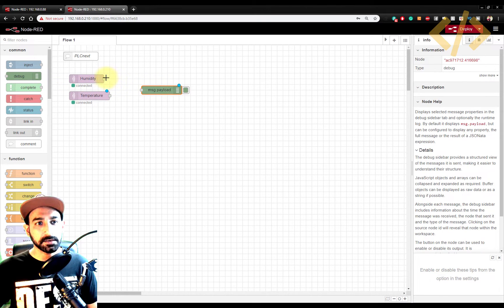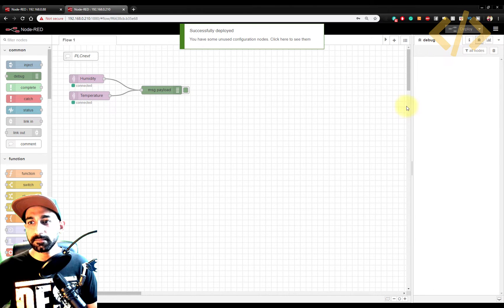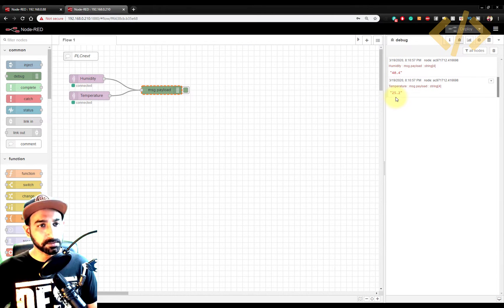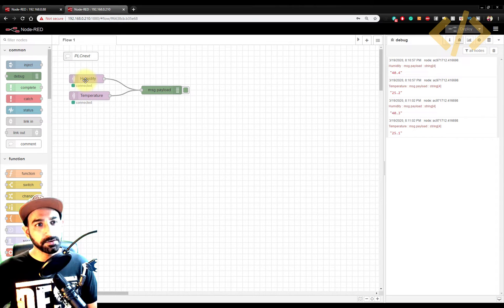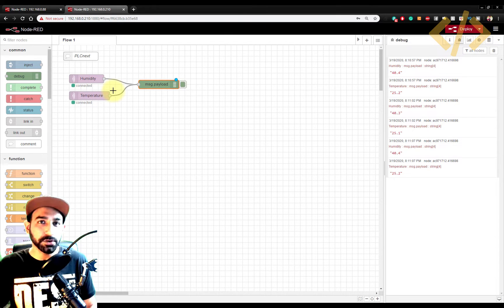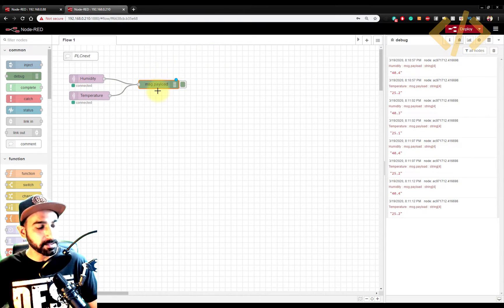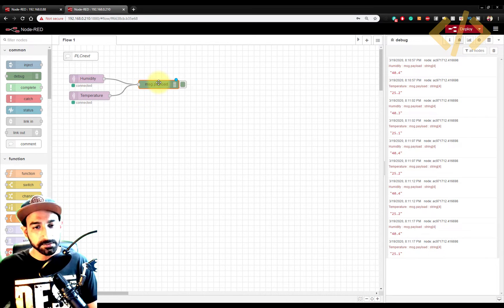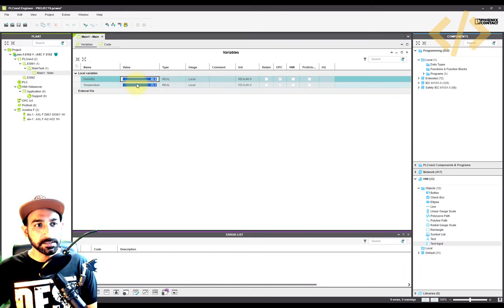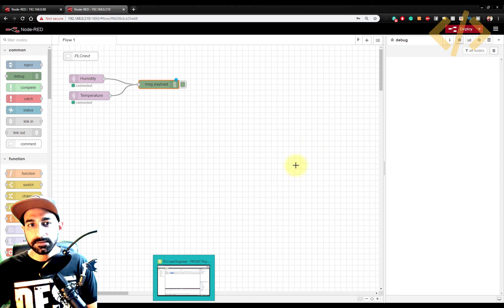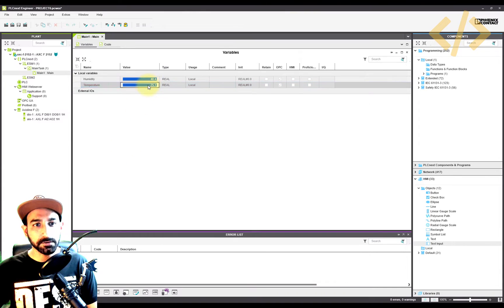Now we have humidity and temperature values coming in. If I want to visualize them I can take a debug node. You can see these two values are coming — 40.4 humidity and 25.2 temperature. So just by writing the topic you are getting the value in your controller. Now you have the values in the Node-RED of PLCnext and you can do whatever you want with them — display them or put them into a variable.